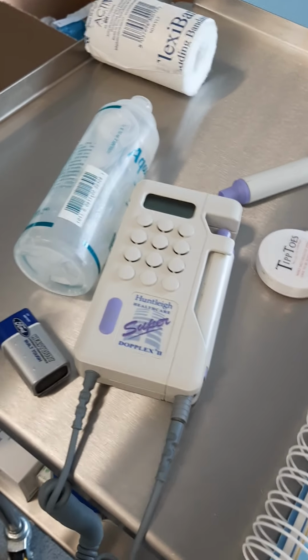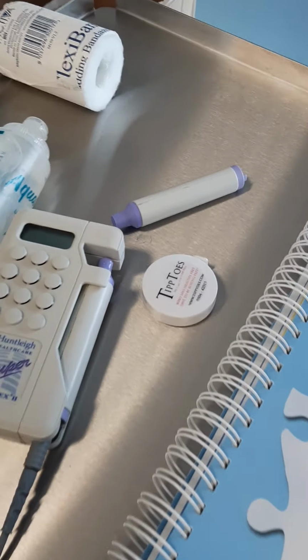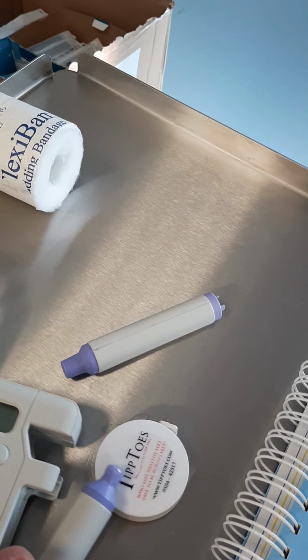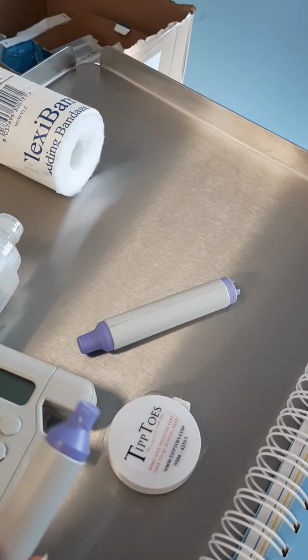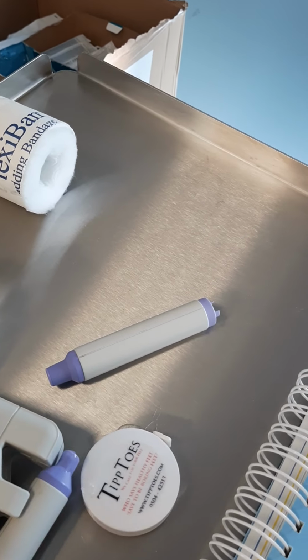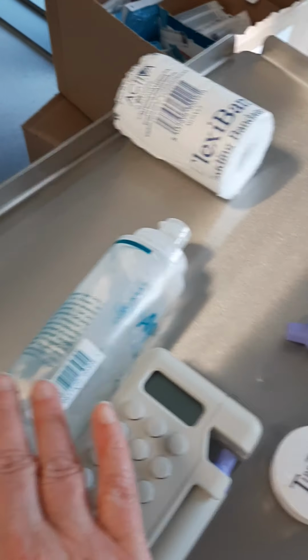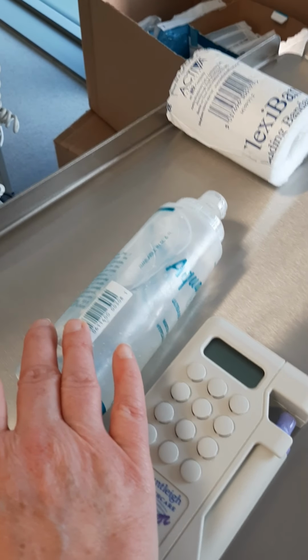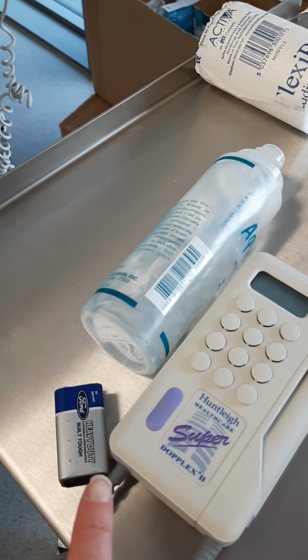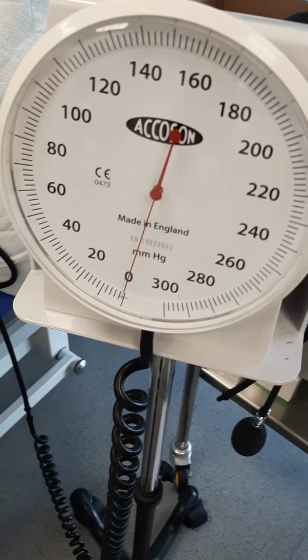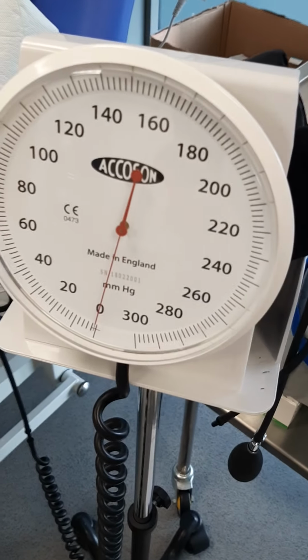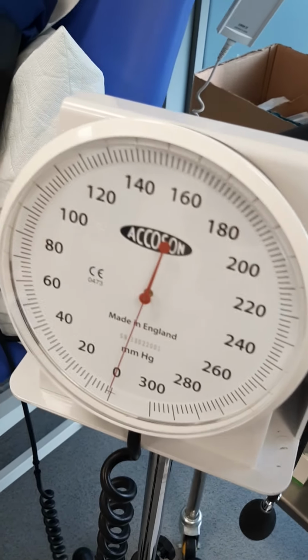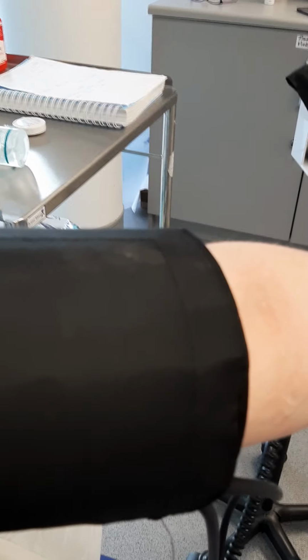So for that, I need my Doppler machine. I need the probes. So I'd always have an 8 megahertz probe and then a smaller dimension probe, which is the 5 megahertz probe. I need my coupling gel to transfer the waves. Always have a spare battery. I have my measuring tape, and then I'd have my sphygmomanometer, and I have my 2 cuff sizes for my sphygmomanometer, a normal size cuff and then a large size cuff for anybody that might have some oedema.